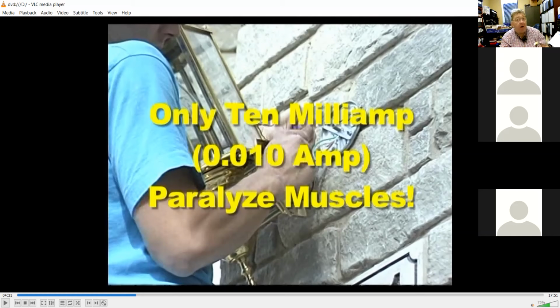So it does have a breaker. It is a breaker, but it trips based on an imbalance of current between the hot wire and the neutral wire if they're not the same. If it's missing current coming back, unaccounted for, and it's in the range of 4 to 6 milliamps or greater, then this trips. And the reason why the trip point on this receptacle is around 4 to 6 milliamps, now listen close here, is because of this number that we see on this screen. What amount of current do you see on the screen right there?